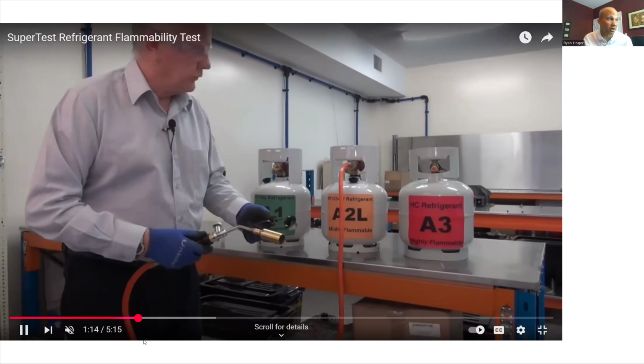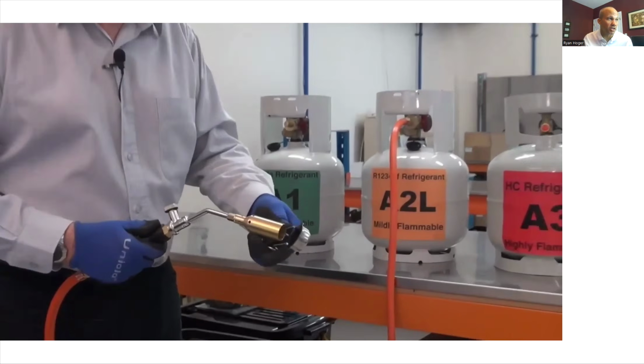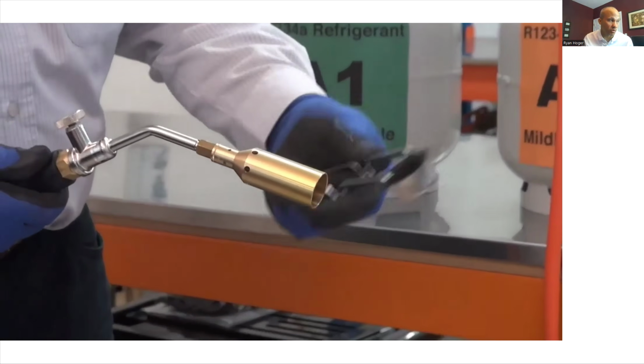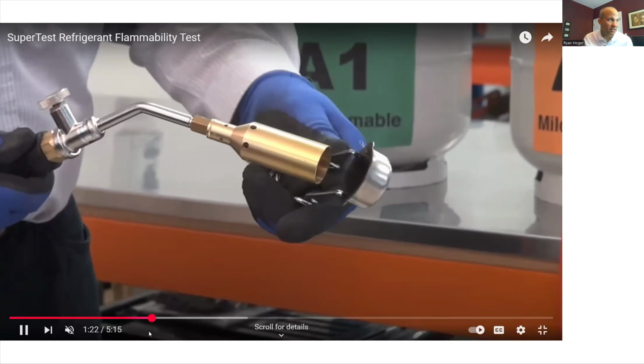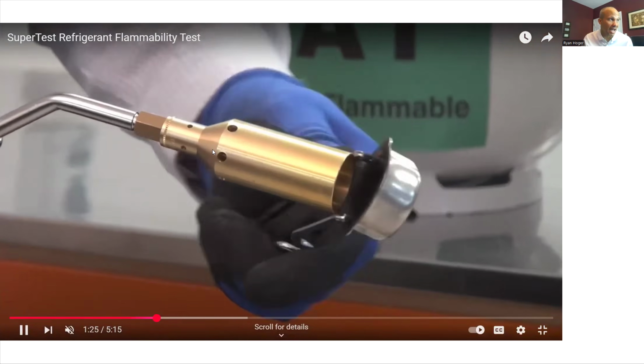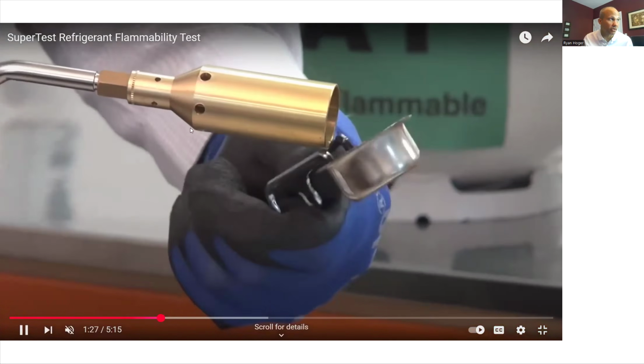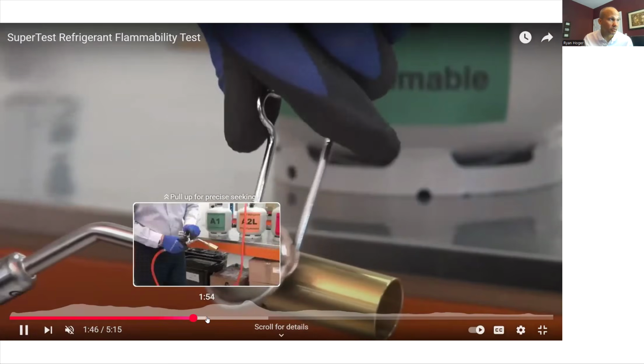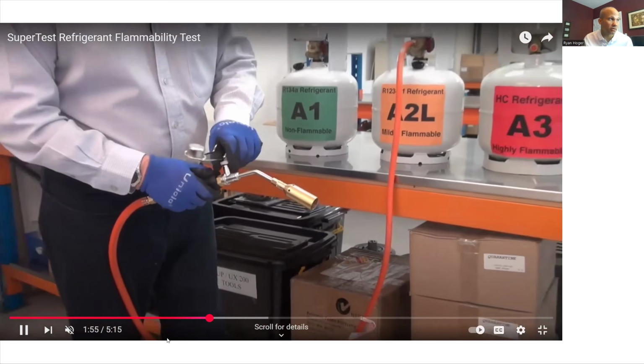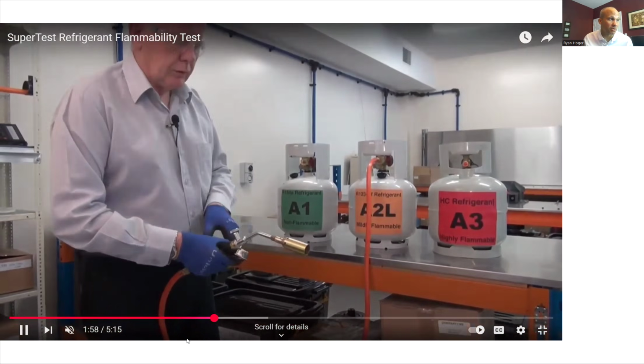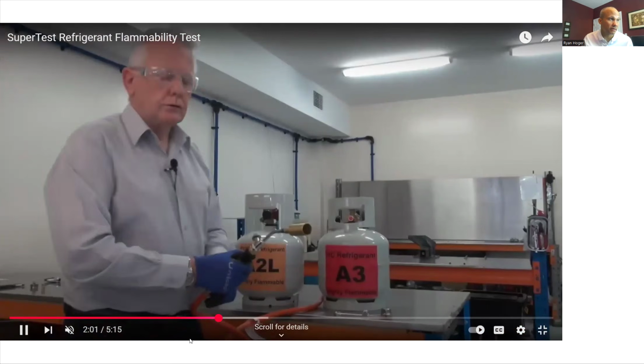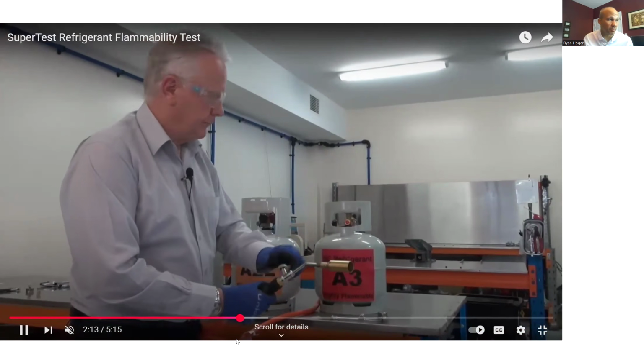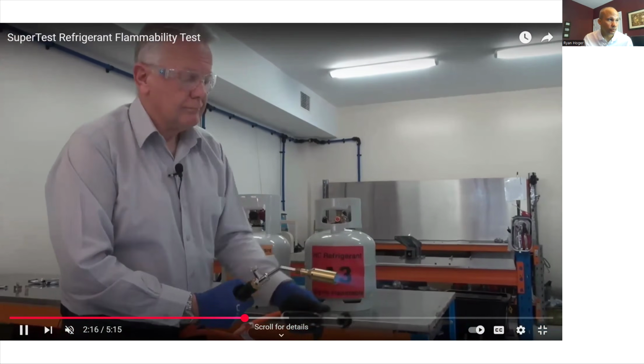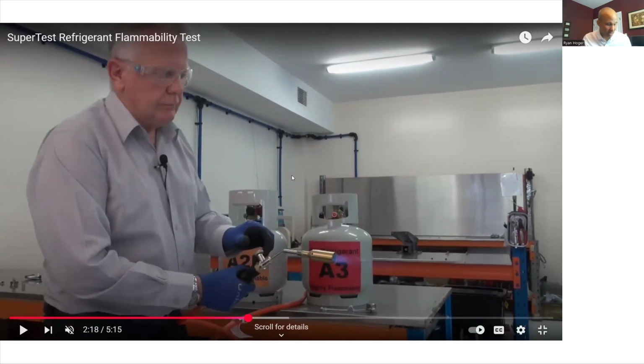In any case, he's got a sparker here. He's got it hooked up to this jug of A2L, which happens to be 1234YF, which is one of the ingredients in R-454B, and he's unable to get it to spark. If you look at the back of the torch, I don't know if you guys can see my little highlighter over there. That's the only place you'll see anything happening. When he turns up the gas flow, which we'll do here in a second, you just turned up the gas flow, try it again, and you're gonna end up with the same result. He's not gonna be able to ignite it with a sparker here. A3, for example, like propane, this will light up immediately. No problem there. That's how hard it is to ignite.